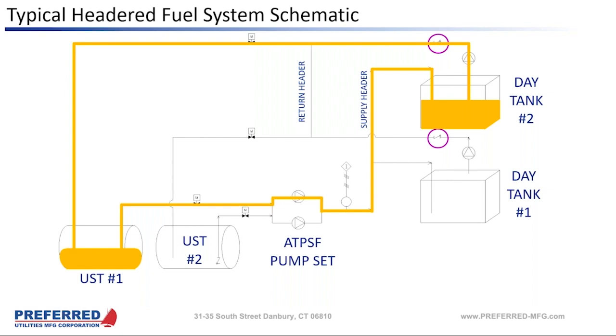storage tank. Also, David, on these, if I could just jump in on the return pump there, especially when we're talking about cold fuel, one of the things that I had to learn in the field over the last 10 years of starting up systems: a lot of gravity returns that are relying just on gravity, that don't have an active return pump, are relying on just the natural head of that fuel to fall back. If we're talking about a system that has a lot of exposed piping or a system in cold weather, those systems already struggle to, quote unquote, gravity return. When you have cold piping and now you add in varying viscosity of fuel, that's going to be even more of an issue.